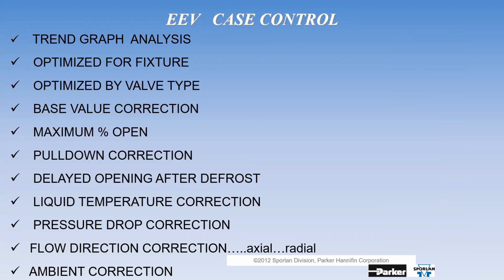Well, why should I let the maximum be 100%? I'm making the valve operator stroke more than it needs to when it opens up. So I can make the maximum opening 38% because I looked at the graph for 3 weeks. It never goes past 38%. I'm going to make that my maximum. If it's not getting down to temperature fast enough, I can do pull down correction. Delayed opening after defrost. Liquid temperature correction.